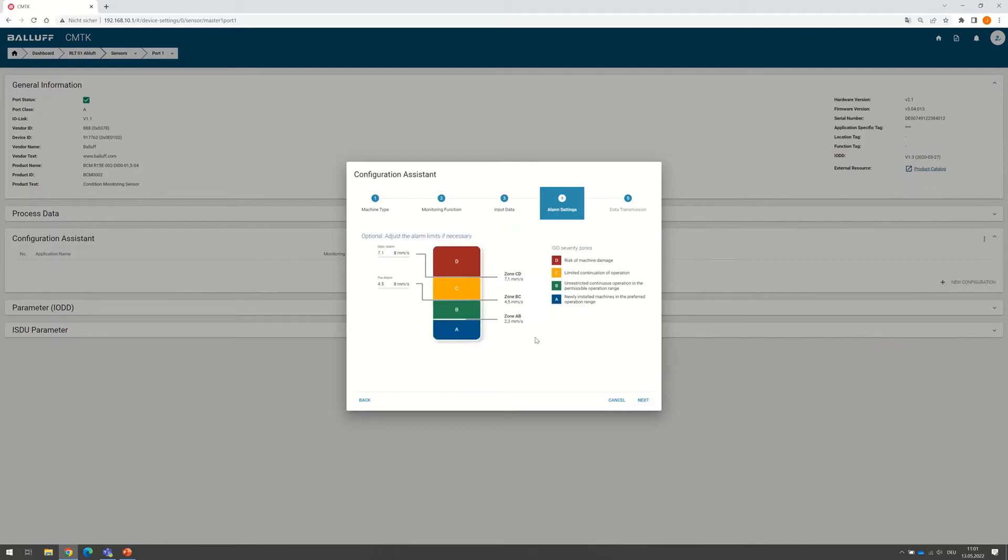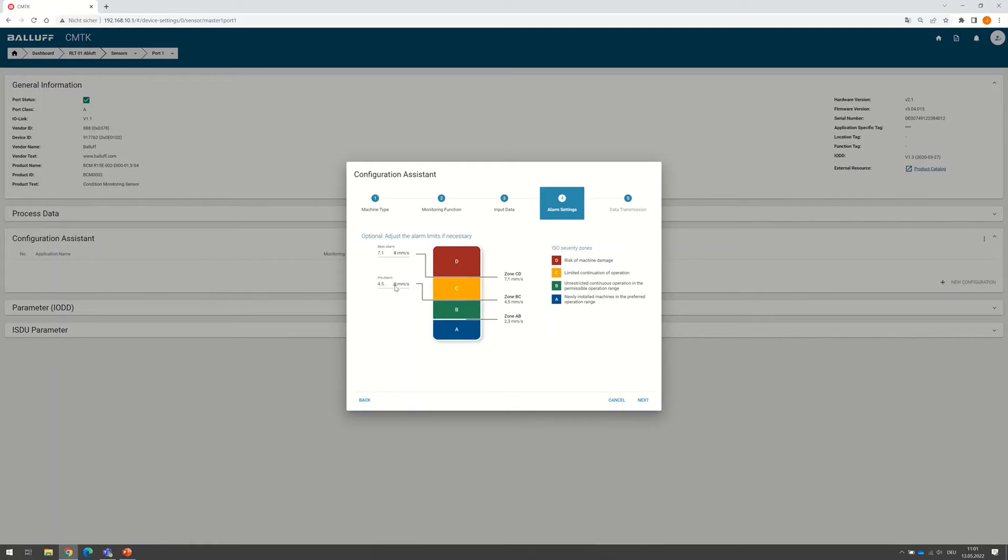And we continue in the window to click next. Now the Configuration Assistant automatically generated the severity zones from the ISO standards and also the pre and the main alarm level. If we want, we can now shift the levels up and down manually. But now we just stick to the ISO standard.